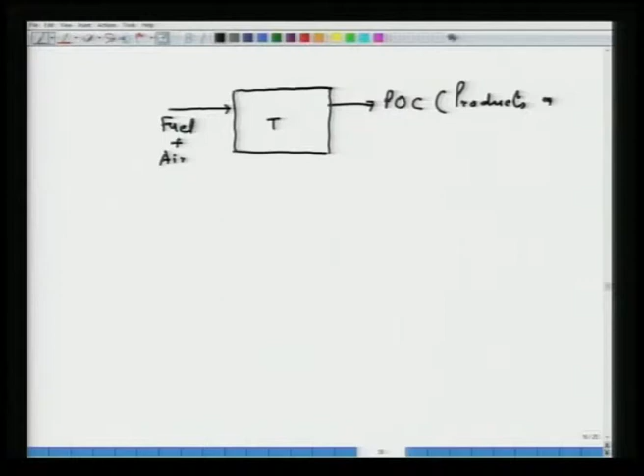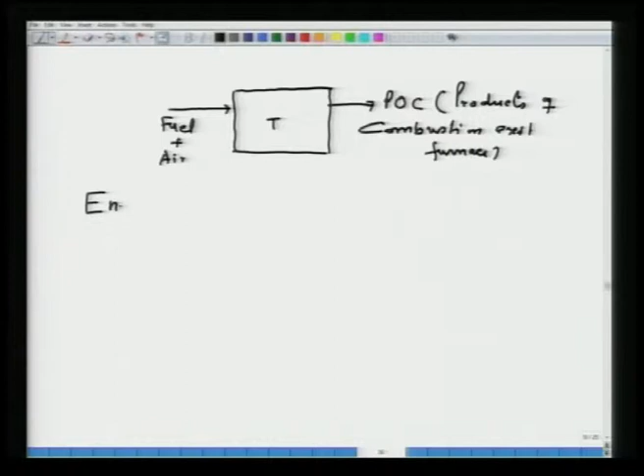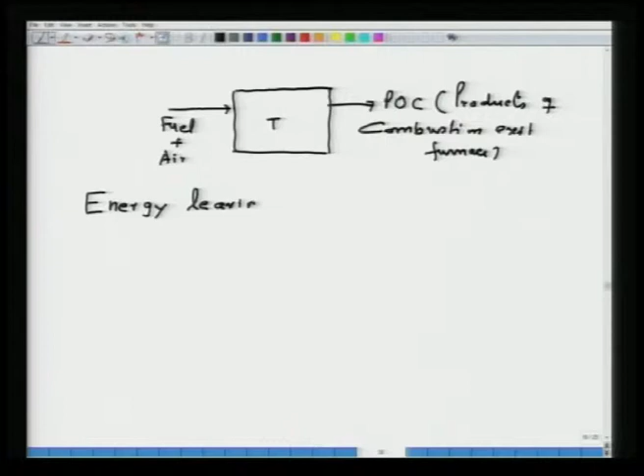That means, if the temperature of the furnace is say 1200 degrees Celsius, then the minimum temperature of the products of combustion exiting the furnace has to be at least 1200 degrees Celsius. If the temperature of the furnace is 1300 degrees Celsius, then the temperature of POC exiting the furnace has to be around 1300 degrees Celsius. What does it mean? That means the energy leaving with POC is not available to perform any thermal energy operation inside the furnace. So, higher the temperature of the furnace, higher will be the energy leaving with POC, and that is not available.